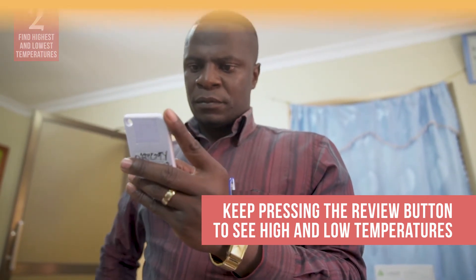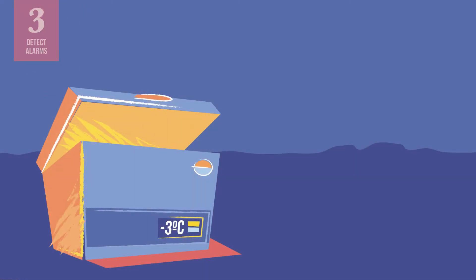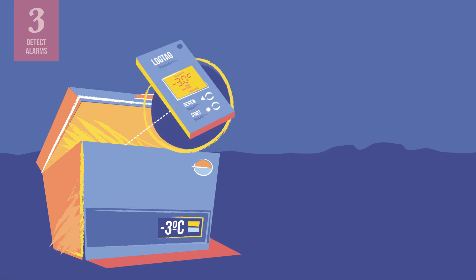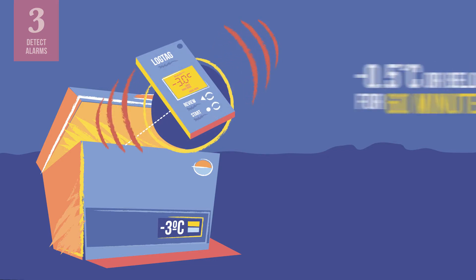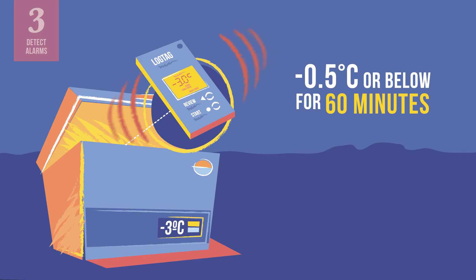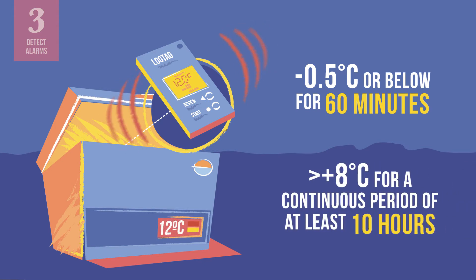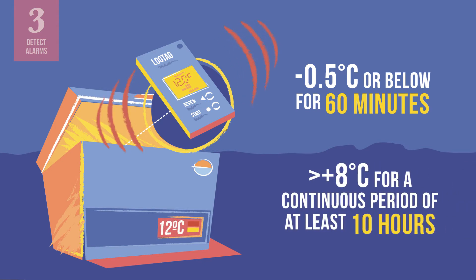You can keep pressing the review button to see high and low temperatures going back day by day for the previous 29 days. The third task is to determine whether any temperature alarms have been triggered and when. Typically, a 30DTR such as the log tag triggers an alarm if refrigerated temperatures fall to negative 0.5 degrees Celsius or below for 60 minutes, or if the temperature exceeds 8 degrees Celsius for a continuous period of at least 10 hours.